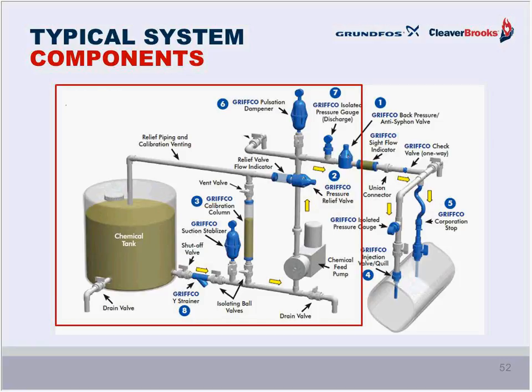Pulsation dampener. Pulsation dampeners are generally installed in dosing systems to ensure smooth, continuous flow and reduce vibrations and stress to the system caused by diaphragm metering pumps. All pumps have a compression and discharge stroke. Pressure spikes are generated by the acceleration and deceleration of the pumped fluid, and may cause the piping to actually shake loose at fittings, possibly even break. Pumps with improved drive technology, such as those stepper motors we talked about, are designed to generate a slow discharge stroke and a quick suction stroke, allowing smooth, continuous dosing without the need of a pulsation dampener. So, check with the pump manufacturer to see if a pulsation dampener is actually required for the pump being installed on a system. And you can end up saving some costs on a pulsation dampener that way.